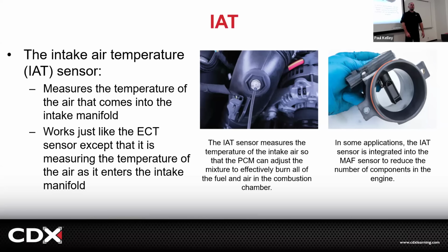It may very well be an intermittent connection up in the sensor like this, but is it possible that it's a connection issue right here at the actual connector with the terminals? It might be in your best interest to check this connection and maybe even check some of your wiring. The challenge with intermittent issues is you can make all your voltage measurements and take all your readings, and if it's working, all your tests will pass. You've got to test it when it's not working to actually find what's missing.